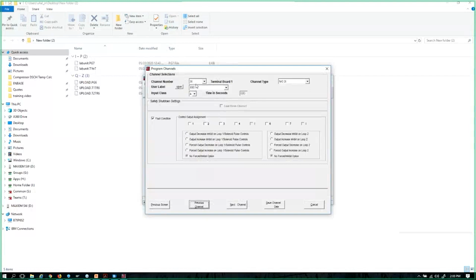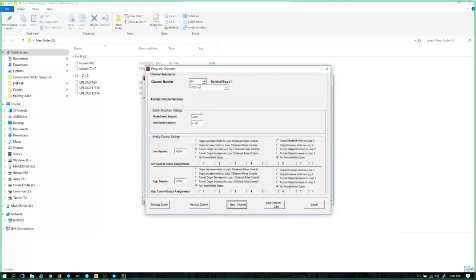So channel 30 is the last channel on this particular system that is truly an input channel as far as channels 1 through 30. If I keep advancing to the next channel, we'll come to SO1. So that's speed 1 input. It's grayed out. We can't change the name. And here's where we could select our underspeed settings and our overspeed. Now this underspeed setting is going to work automatically about like a Class C timer.